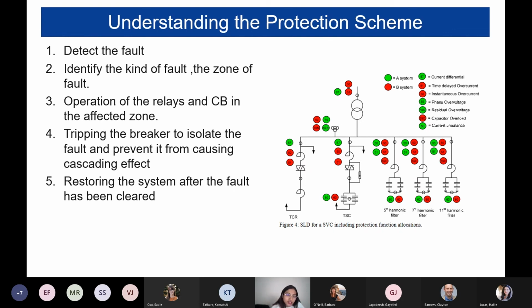Basically, you need to detect the kind of fault you're dealing with. Then you need to identify the zone of the fault, as in which area you need to focus on, which equipment needs to be protected, how it needs to be protected, what kind of relays and circuit breakers need to be set up, so the fault is quenched and doesn't travel through the system causing cascading effects and damaging other equipment.